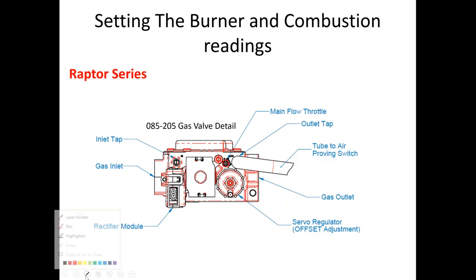This is the detail of the gas valve. Right here is our offset. Right here is our throttle screw. We want to make all the big adjustments on this throttle screw. If you read the instructions, it's going to tell you to move this throttle screw in 1/4 inch to 1/8 inch turns, a little bit at a time. That throttle screw is not as sensitive as the manual makes it out to be. If you get the pleasure of having me come out to do one of the startups, it's usually a half to a full turn is where I start turning with that.